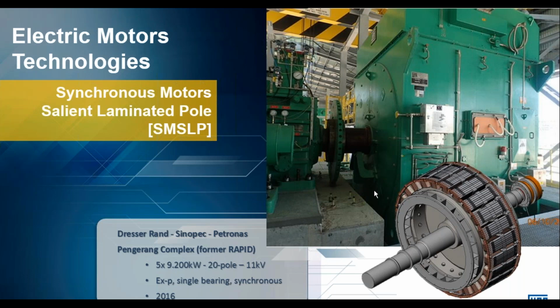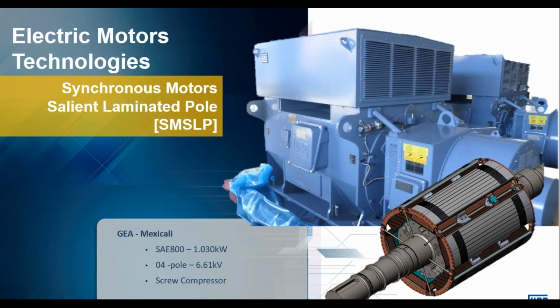These kind of synchronous machines, at least, are very common in the high power, slow speed, in other words, large number of poles designs. This particular example is a 9.2 megawatt 20 pole design. However, they can also be constructed in high speed designs. You're looking here now at a 4-pole design of the same construction type.